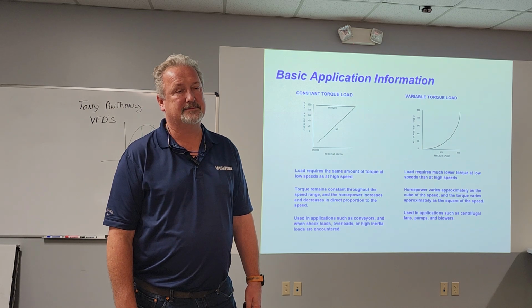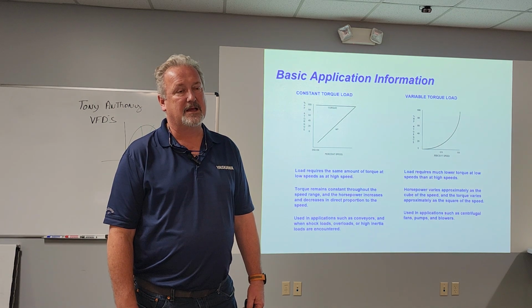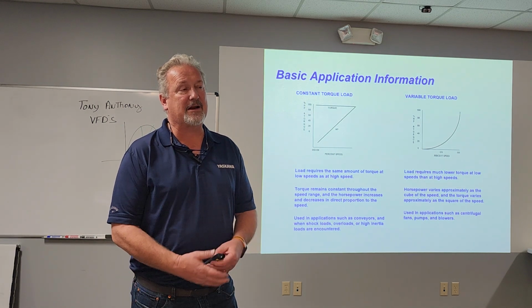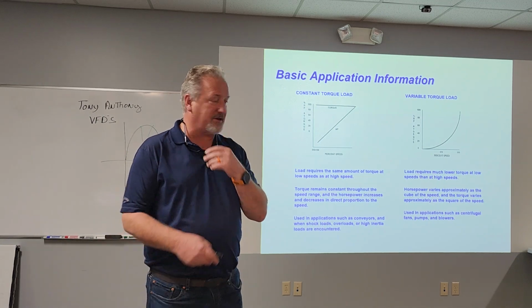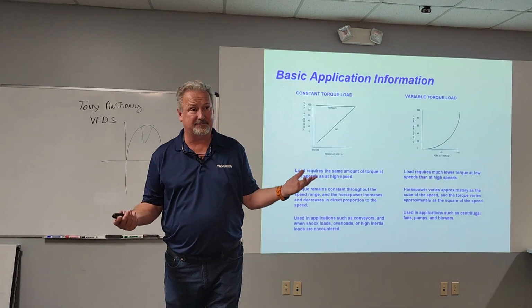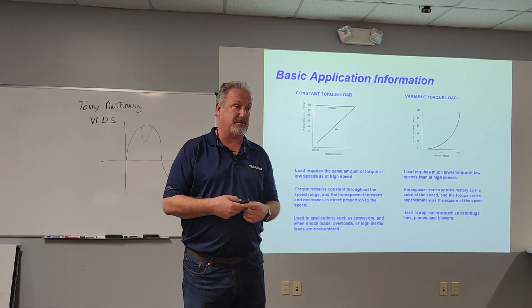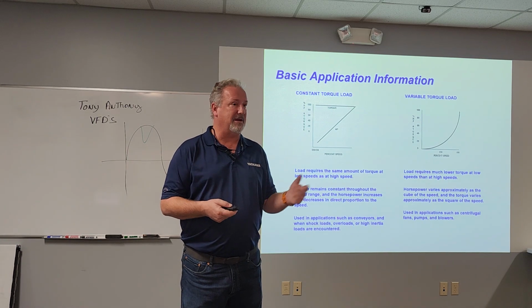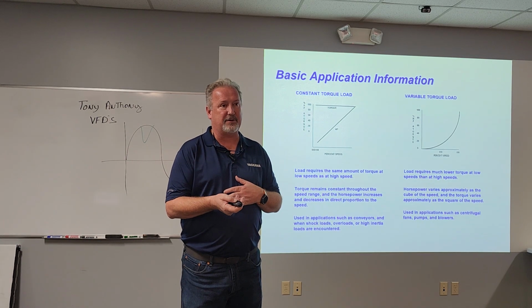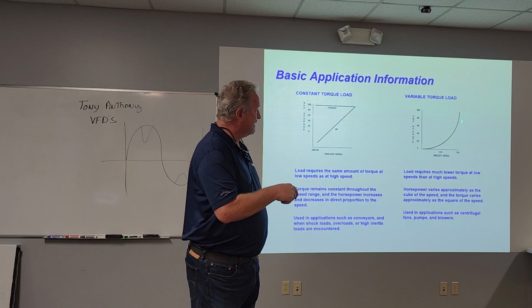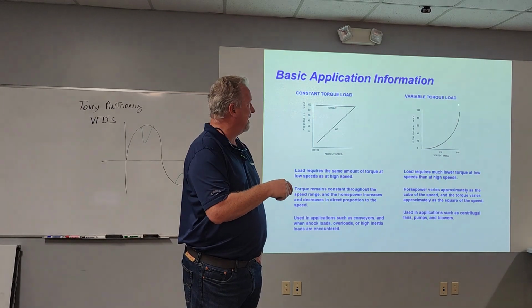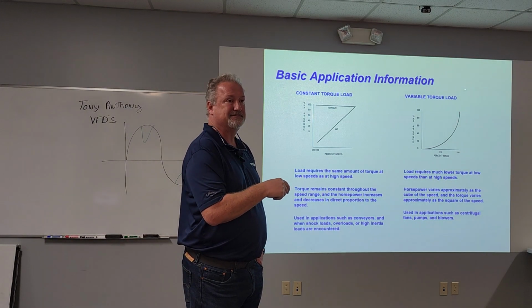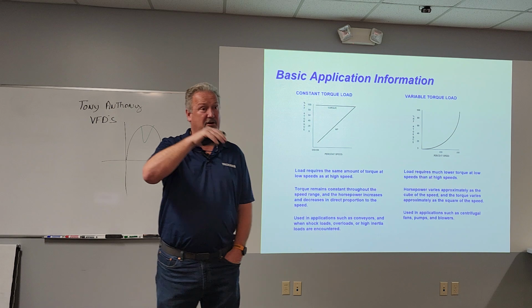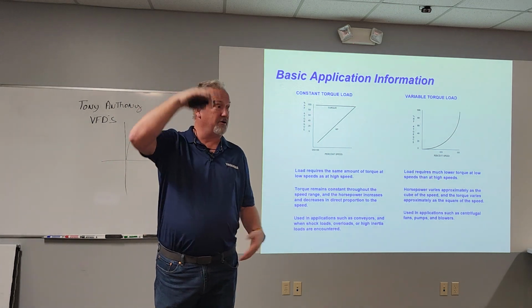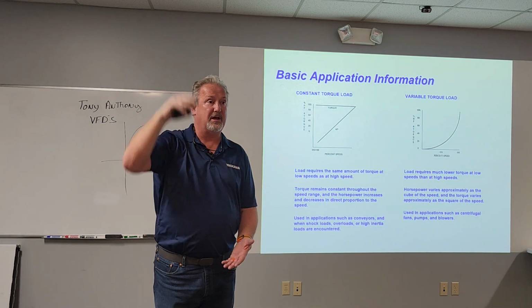I mean, it's 80 hertz. Yeah, 80 hertz. And the thing you've got to watch with that: you can run our drives up to over 400 hertz, I mean, over 500 hertz. Sure, but there's a certain point you've got to be careful, because just like this little bit changes here, as soon as you get above 60, that's almost a straight line up. So as you start going 70 hertz, the power is just going through the roof.